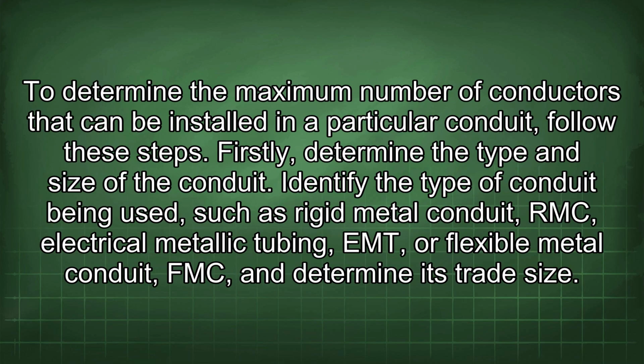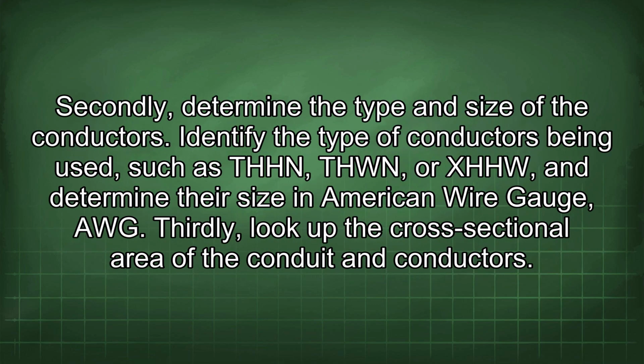To determine the maximum number of conductors that can be installed in a particular conduit, follow these steps. Firstly, determine the type and size of the conduit. Identify the type of conduit being used, such as rigid metal conduit, RMC, electrical metallic tubing, EMT, or flexible metal conduit, FMC, and determine its trade size. Secondly, determine the type and size of the conductors. Identify the type of conductors being used, such as THHN, THWN, or XHHW, and determine their size in American wire gauge, AWG.